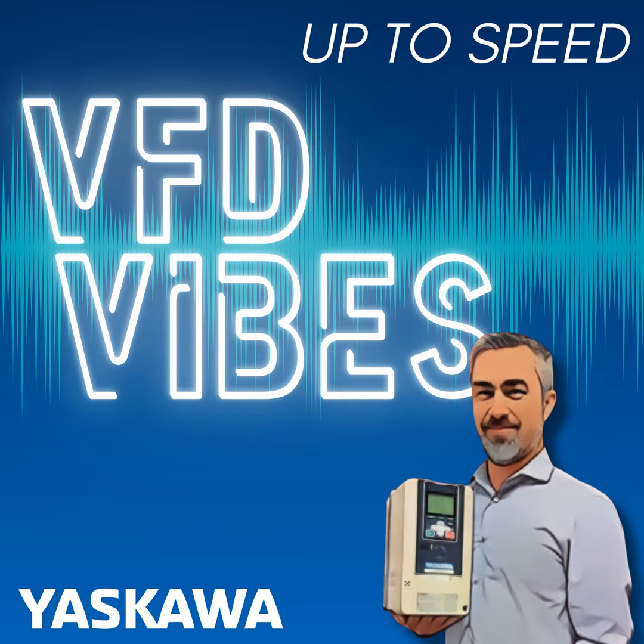So you can have a line to ground fault, and unless you have some special equipment to detect it, it would go undetected. You still measure 480 volts line to line. Now, if you have two line to ground faults on two different phases, well, now you got a line to line fault, that pops the breaker and everything's done. So the way this is typically done is they will measure the current in the grounding resistance. And if you see current flowing in the grounding resistance, that means that you have some kind of a line to ground fault, or you have excessive leakage in one of the lines to ground.